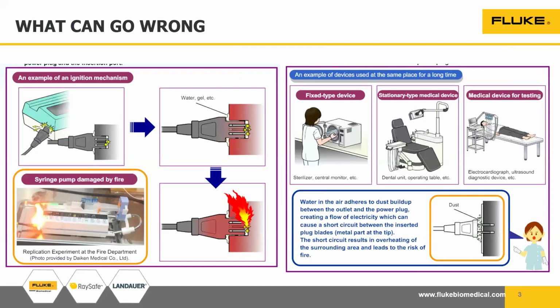So what are the things that generally on a broader scale can go wrong? There can be fire incidences, because as Gopa was telling, water and gel create a highly conductive environment in a hospital. These kinds of incidences can happen when water and dust build up in connections, and that can also create fire incidents from various medical or non-medical devices connected or installed in a hospital.